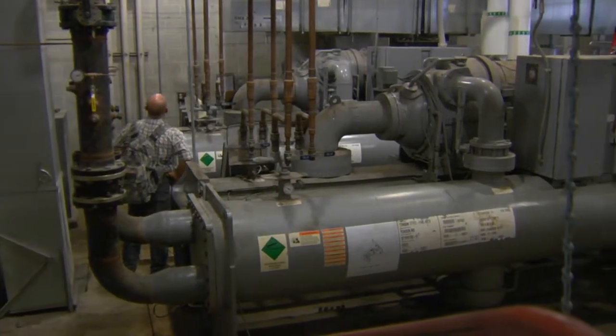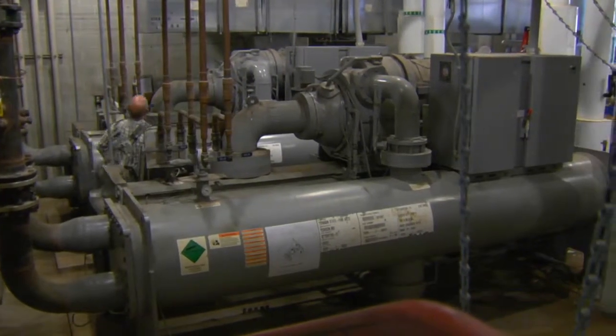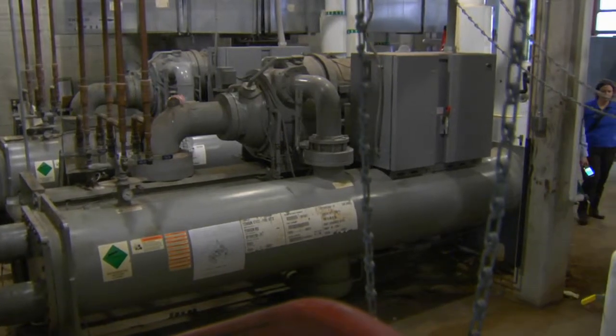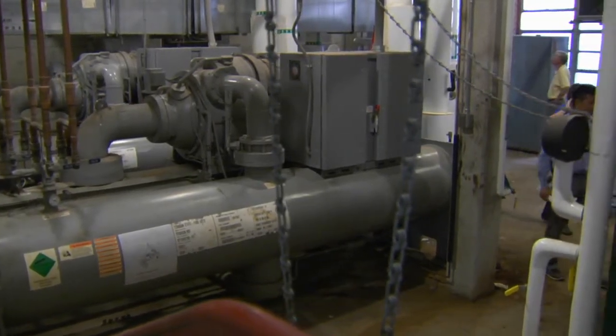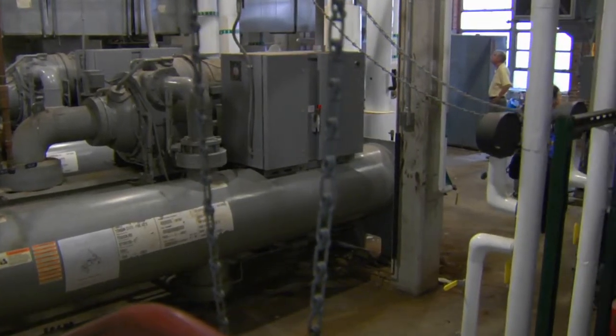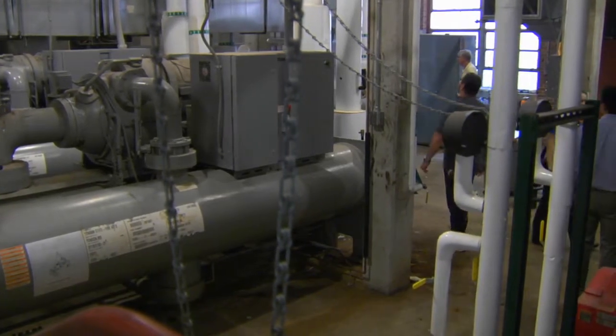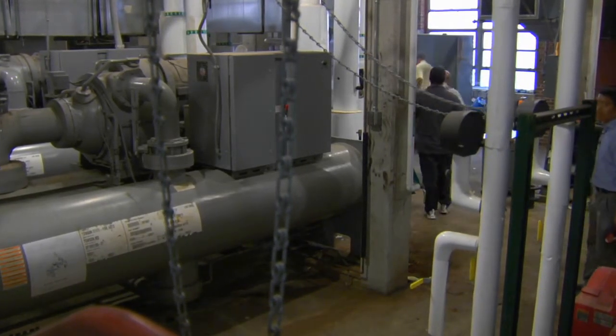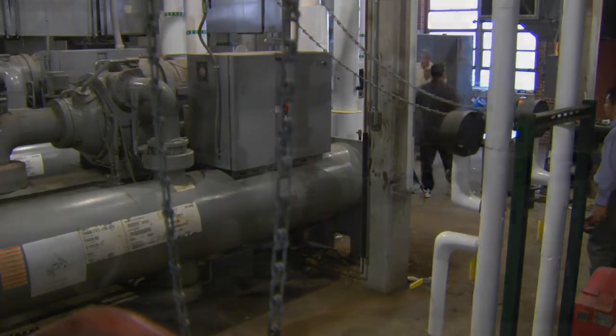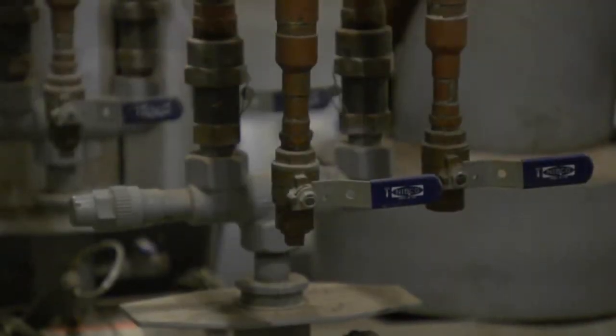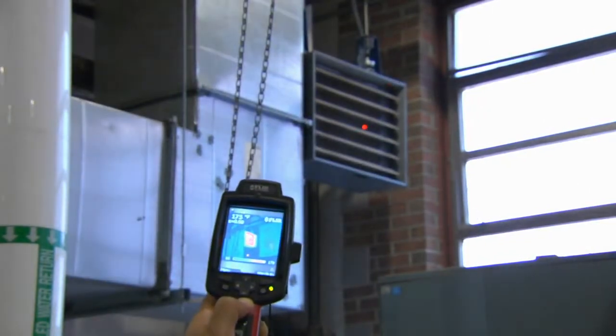Isolation valves were 50% closed with a piping system design with VFD-driven pumps. This creates additional pressure drops in the system, and it doesn't allow the plant to take advantage of the VFD-driven pump capabilities. We recommend putting the isolation valves back to the original design configurations. The current configuration should not be a long-term solution.